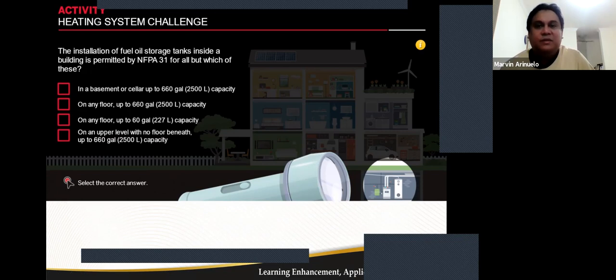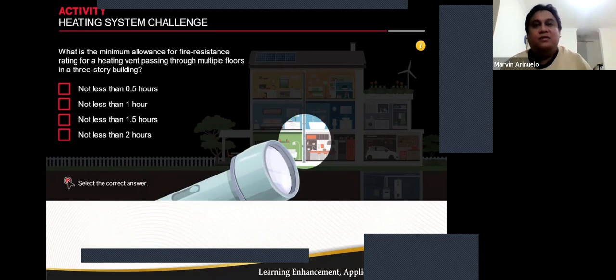Next, the installation of a fuel oil storage tank inside the building is permitted by NFPA 31 for all but which of the following? All of the choices are permitted by NFPA 31, except any floor up to 660 gallons or 2,500 liters capacity. NFPA permits installation of a tank inside a building on any floor only up to 60 gallons or 227 liters capacity. So the exception answer is B, up to 660 gallons or 2,500 liters, according again to your NFPA handbook. I already extracted the relevant section for you in advance prior to this class.